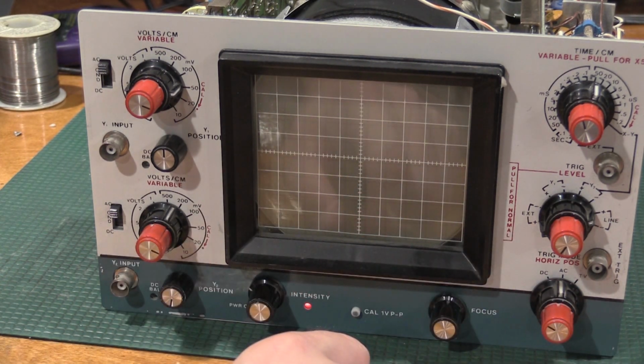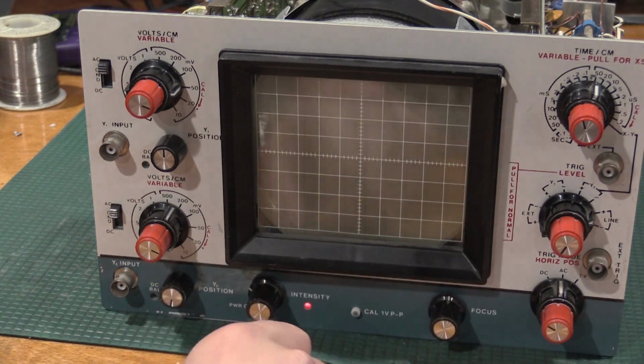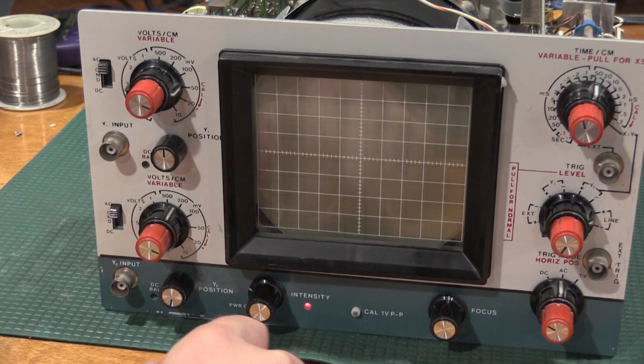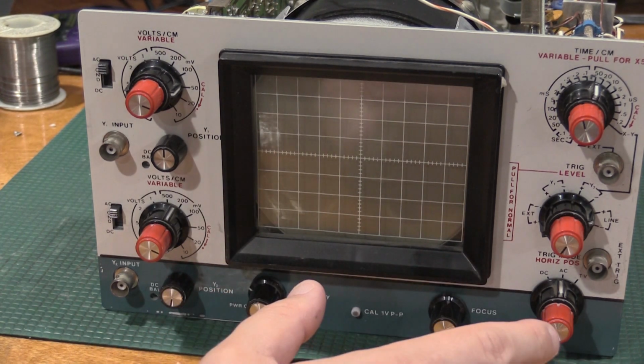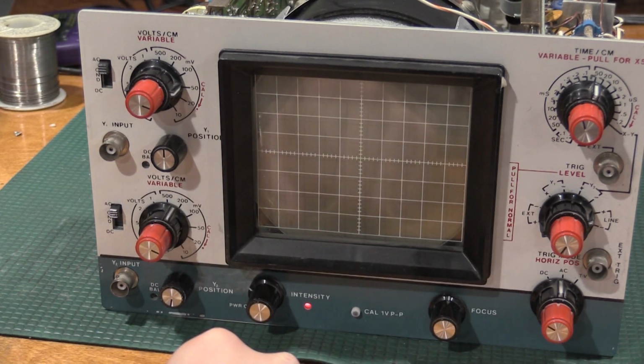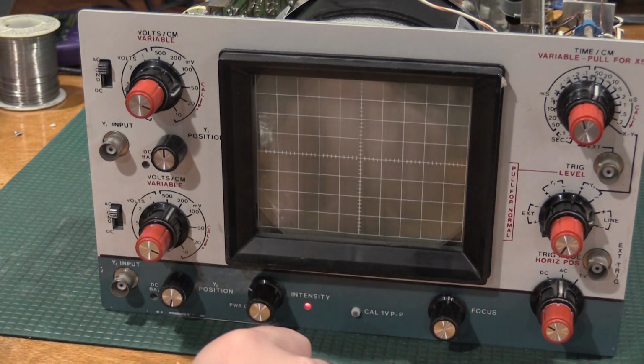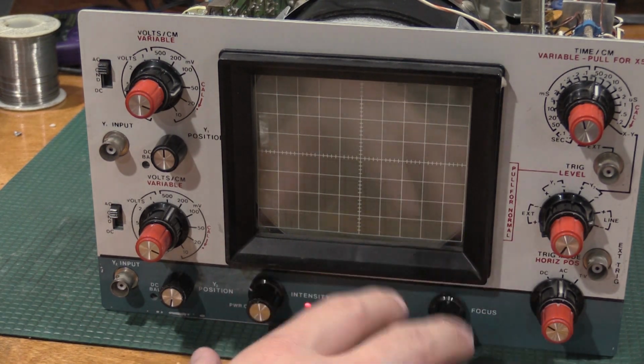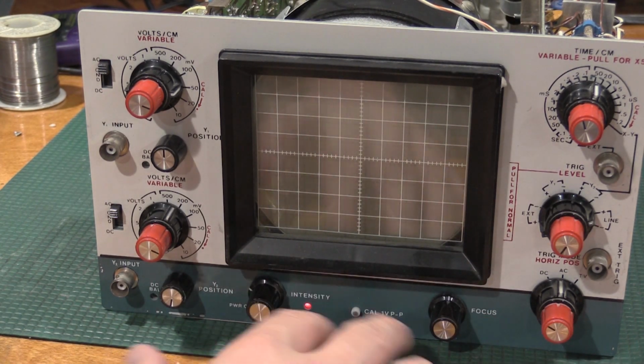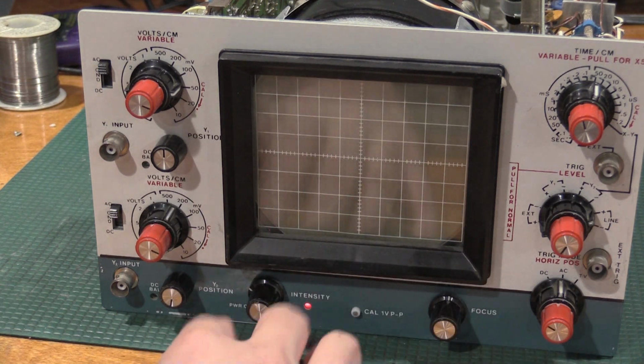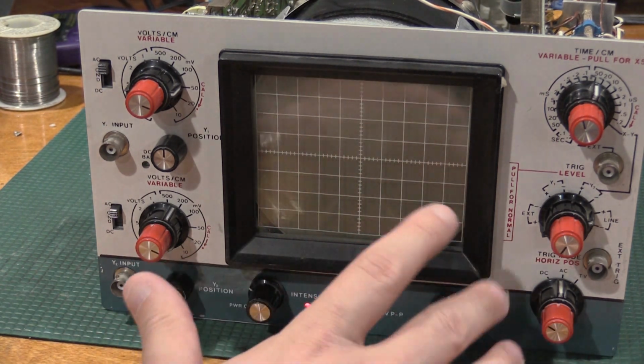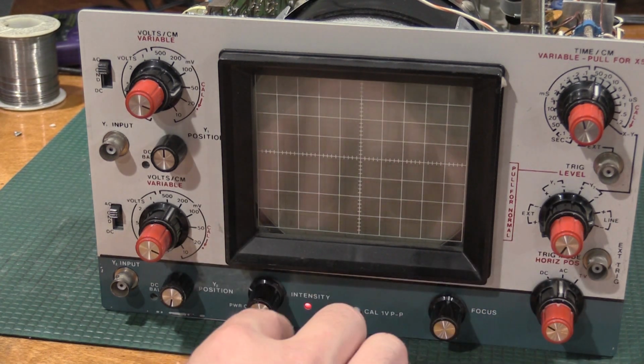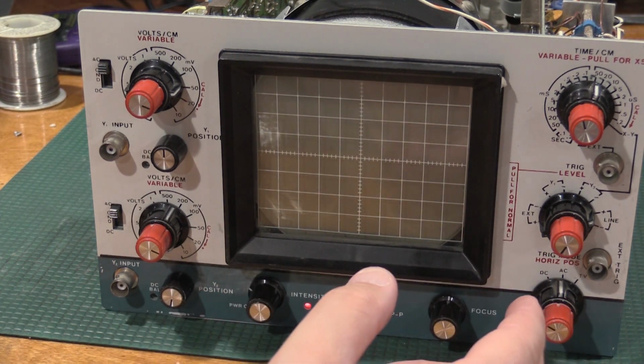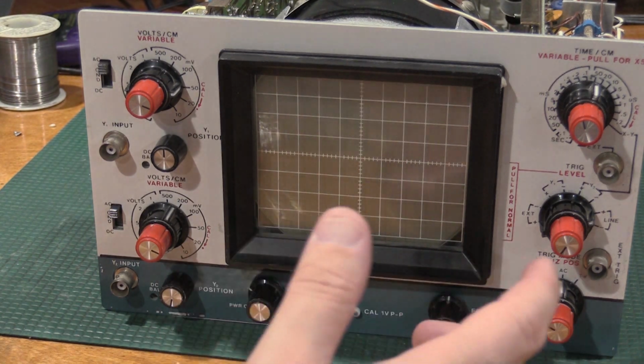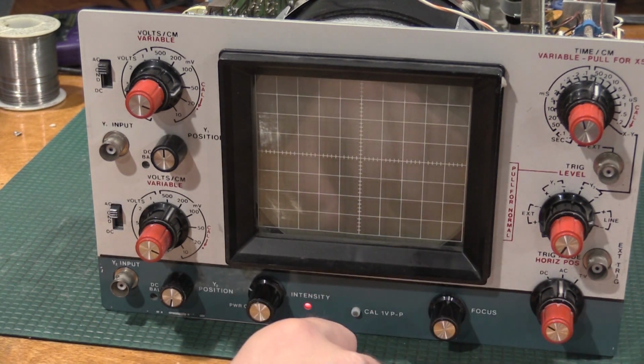Acceleration voltages in Tek scopes and things like that can hit 26, 27, 30 kV. So, 30,000 volts. We're starting to get into some spicy voltages there. When I do the alignments on the Tek scopes, we actually measure the high voltage supply pre-multiplier. So even pre-multiplier, it's 4-ish odd thousand volts negative. Then you kick it through a 3-4x multiplier or more, and you have a spicy meatball.